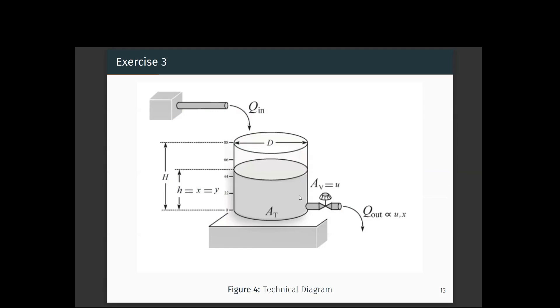The alternative second way of controlling this tank is by giving a control instruction U to the valve at the outflow. Here the inflow is constant and we sense the height of the tank, send it to the controller, and the controller instructs the outflow valve. If the desired height is 66 and the present height is 50, it closes the valve more so that the level gradually rises to the set point. So either we control the inflow or the outflow of the tank to achieve the desired set point. The controlled variable is the height of the tank, and the manipulated variable is the instruction given to either the inflow or outflow valve.